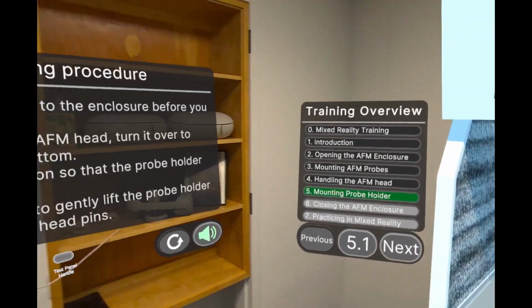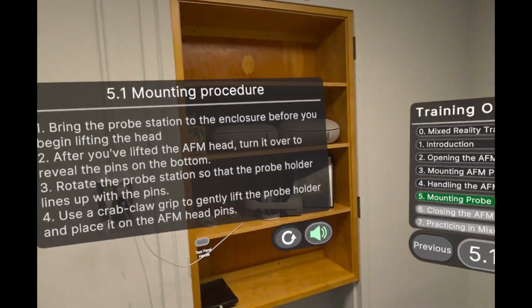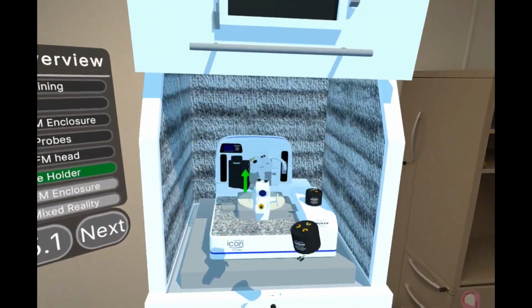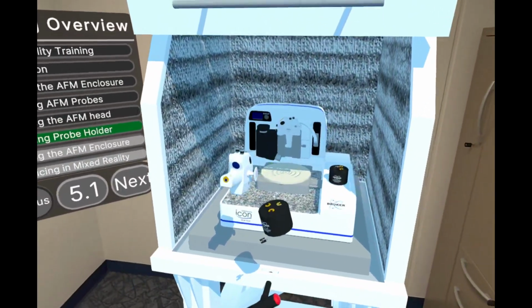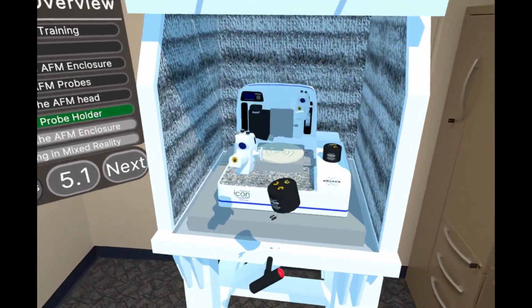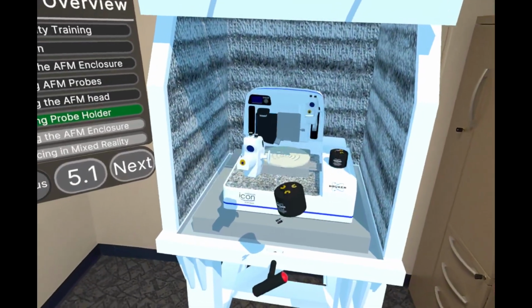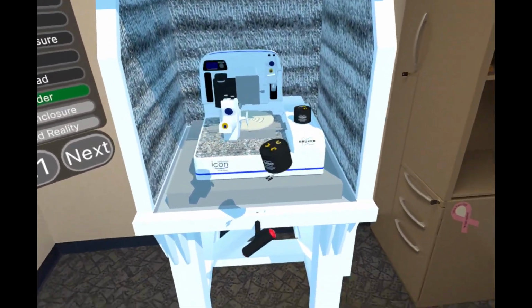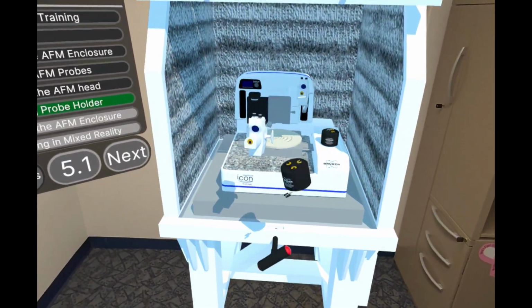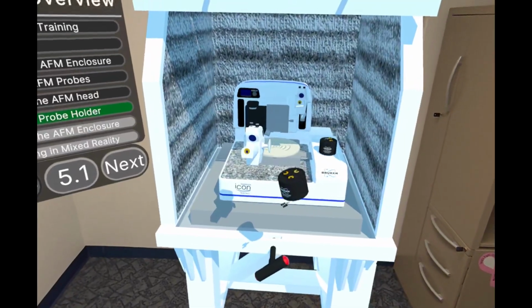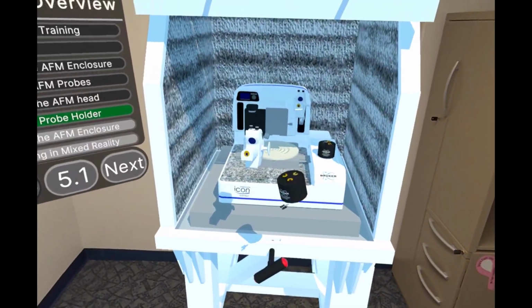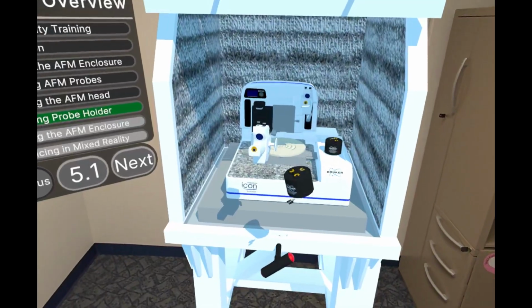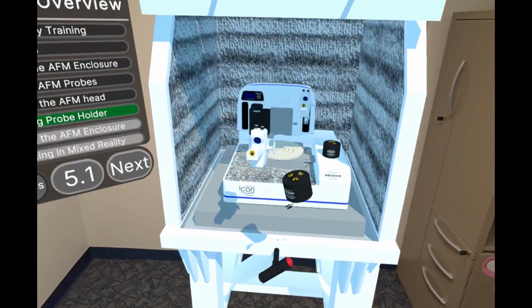Mounting the probe holder onto the AFM head. Turn the head over gently and you'll see 4 brass pins. They bend easily, so be careful to keep them clear of all surfaces while the AFM head is in your hand. The entire circular area on the bottom of the AFM head is connected to the piezo scanner, so any impact will damage both the pins and the piezos.